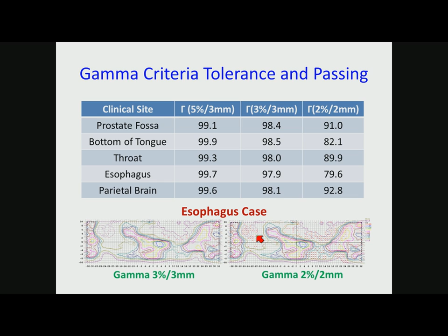But you change it to 2%, 2 millimeters, look at the esophagus case. Suddenly the passing rate dropped to 80%, a big drop. And now you can see, this is an ArcCheck, which is what we used here for this study, and you can look at all the diodes which are on the harder side. So there's a slight difference between 3% and 2% on the ArcCheck, and obviously your gamma is off. So you've got to go back and look at why that is happening. You need to stop and pause and see what's going on.